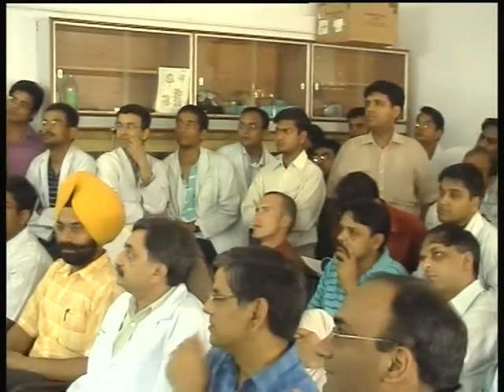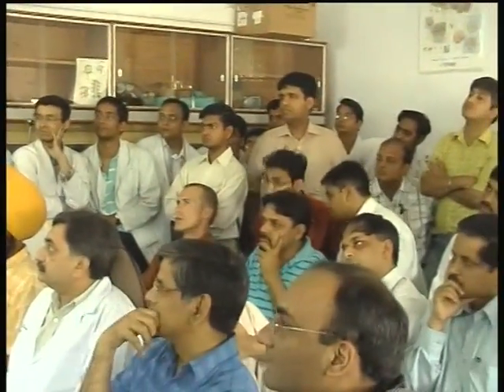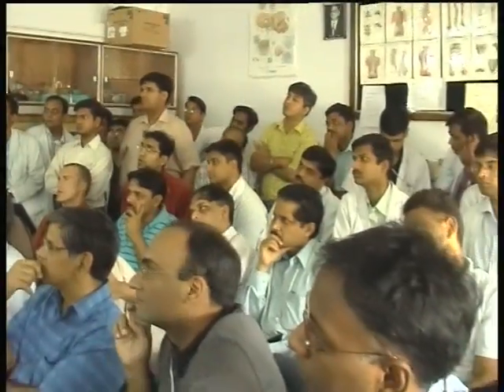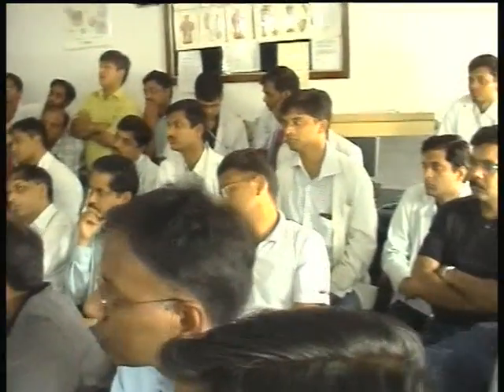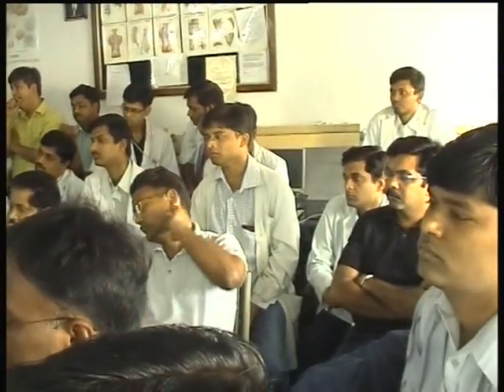These protection tubes are very, very important. Always, all the neuroendoscopy equipment or the fine optics should be used with this. You can really imagine that if it falls, the rod lenses are going to break. So it becomes very important to use the protection tube.